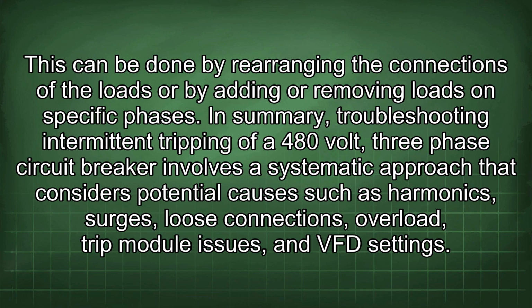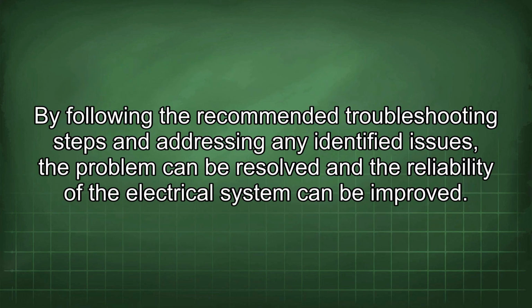In summary, troubleshooting intermittent tripping of a 480-volt, three-phase circuit breaker involves a systematic approach that considers potential causes such as harmonics, surges, loose connections, overload, trip module issues, and VFD settings. By following the recommended troubleshooting steps and addressing any identified issues, the problem can be resolved and the reliability of the electrical system can be improved.